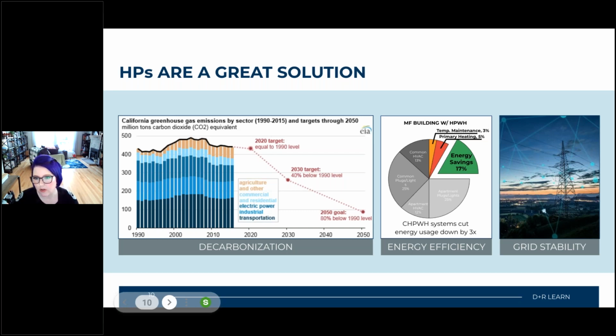The middle picture is a pie graph from a study on a domestic hot water application in a multifamily building. Engineers went in, measured the energy usage, and found the domestic hot water system was accountable for about 25% of the building's energy use. They switched out a traditional gas boiler system with a heat pump water heating system, and pretty quickly there were significant energy savings—about 17% of the energy was saved in the overall building.